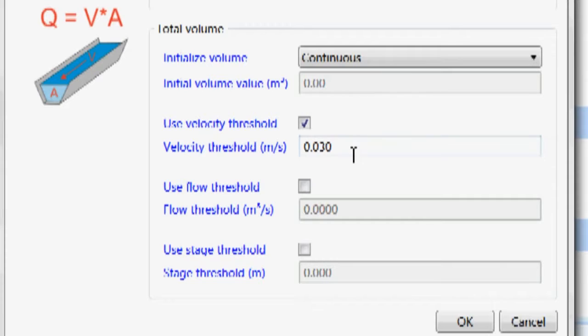Some irrigation canals, when they're not operating—if the gate's closed or the pumps are off—the water will slosh around. We can set a lower velocity threshold, flow threshold, or stage threshold so that once it goes down to this minimum value, it will not compute a volume. That's just a practical setting to avoid adding flow when, for example, the IQ is installed upstream of a gate and the gate is shut, causing flow to slosh back and forth.